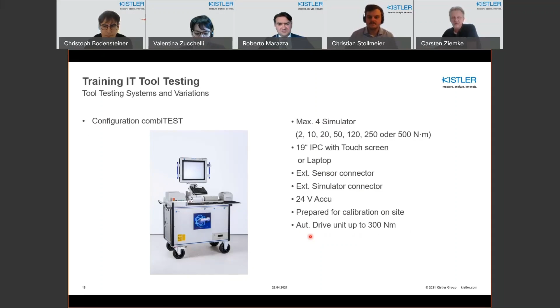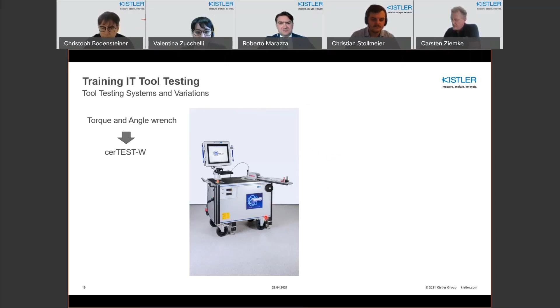And Roberto also showed other torque wrenches, display wrenches. This is a torque and angle wrench. And therefore, if you want to test the angle, you have to move the tool. Therefore, we developed the cerTEST-W. In this case, you see an arm where you can put in the wrench, and for testing this, you bring the system to a start position, and after that the system moves this arm, because the torque and angle wrenches have a gyroscope inside to measure the angle, and this gyroscope only works if you move the arm. Therefore, we have this arm, and we move it, and the torque and angle wrench can measure the torque and also the angle.